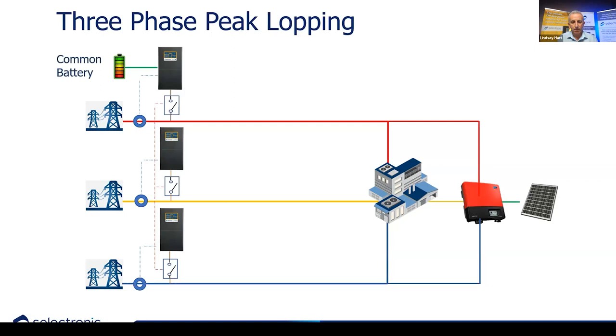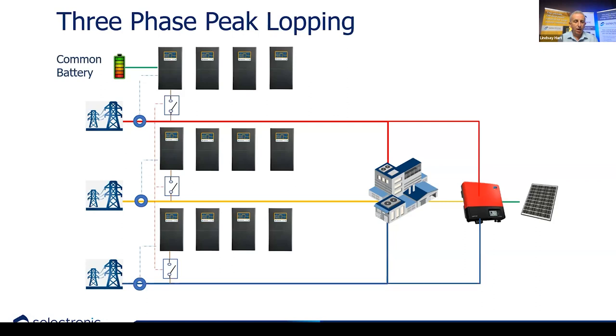The nice thing about this system is we could add another set of three-phase inverters, another set as well. We could go up to 240 kilowatts of continuous power. The fact that the SP Pro is an industrial-grade product rather than a domestic-grade product, it suits this kind of application extremely well, because what we're trying to do is make sure that when that power is needed, it's delivered.